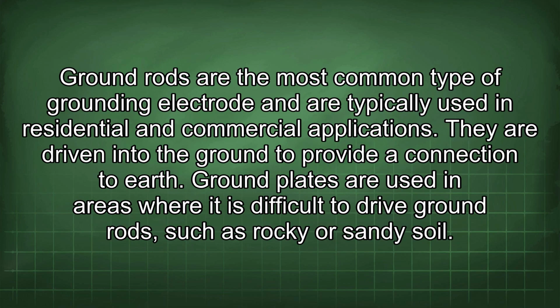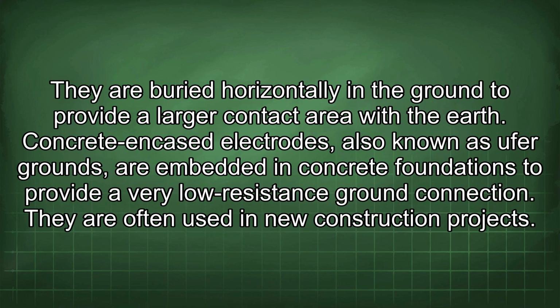Ground rods are the most common type of grounding electrode and are typically used in residential and commercial applications. They are driven into the ground to provide a connection to earth. Ground plates are used in areas where it is difficult to drive ground rods, such as rocky or sandy soil. They are buried horizontally in the ground to provide a larger contact area with the earth. Concrete encased electrodes, also known as UFER grounds, are embedded in concrete foundations to provide a very low resistance ground connection. They are often used in new construction projects.